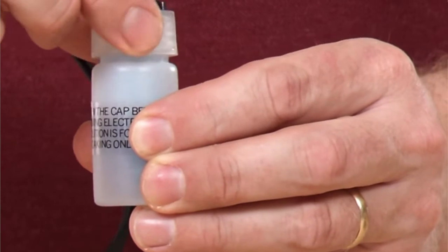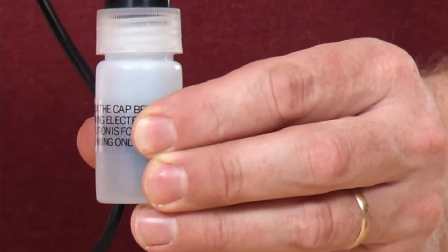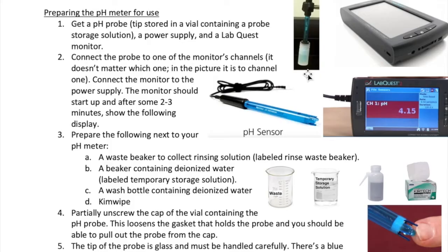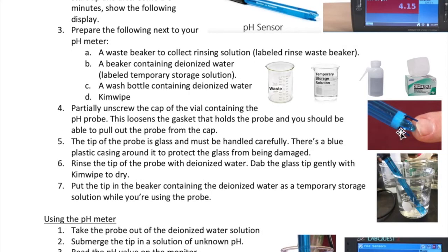Partially unscrew the vial where the pH probe tip is stored. Pull the pH probe out and screw the cap back onto the vial. The tip of the probe is made out of clear glass, which is protected by the blue plastic casing. The glass can break, so you need to handle it carefully.